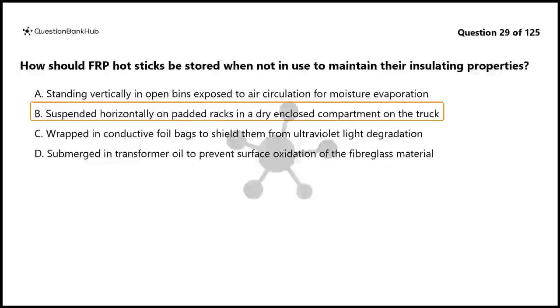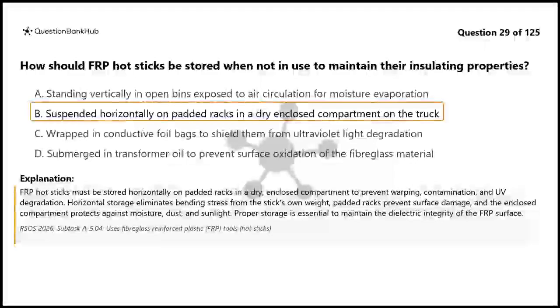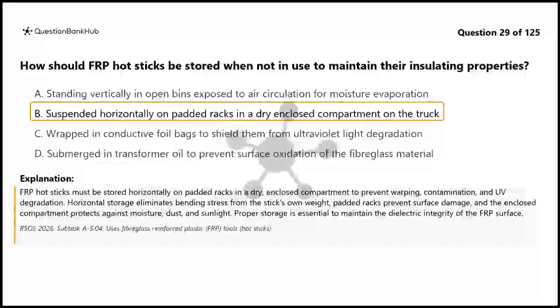The correct answer is B. FRP hot sticks must be stored horizontally on padded racks in a dry, enclosed compartment to prevent warping, contamination, and UV degradation. Horizontal storage eliminates bending stress from the stick's own weight, padded racks prevent surface damage, and the enclosed compartment protects against moisture, dust, and sunlight. Proper storage is essential to maintain the dielectric integrity of the FRP surface.